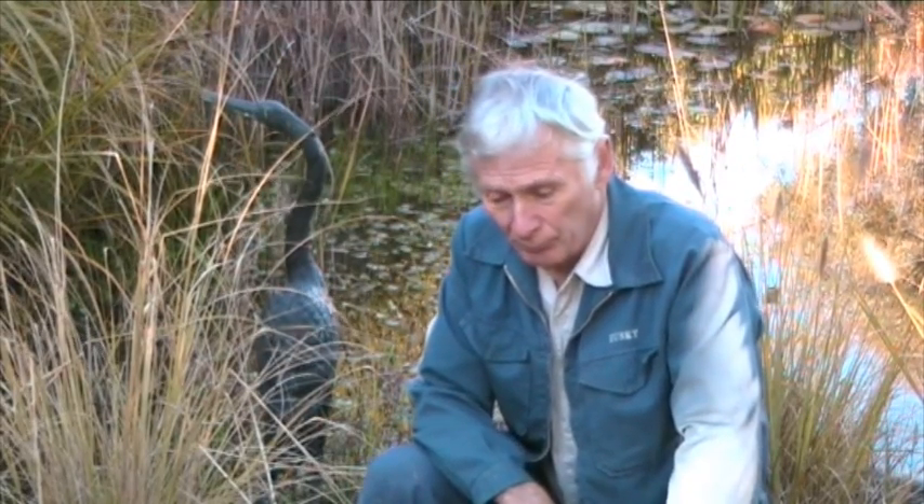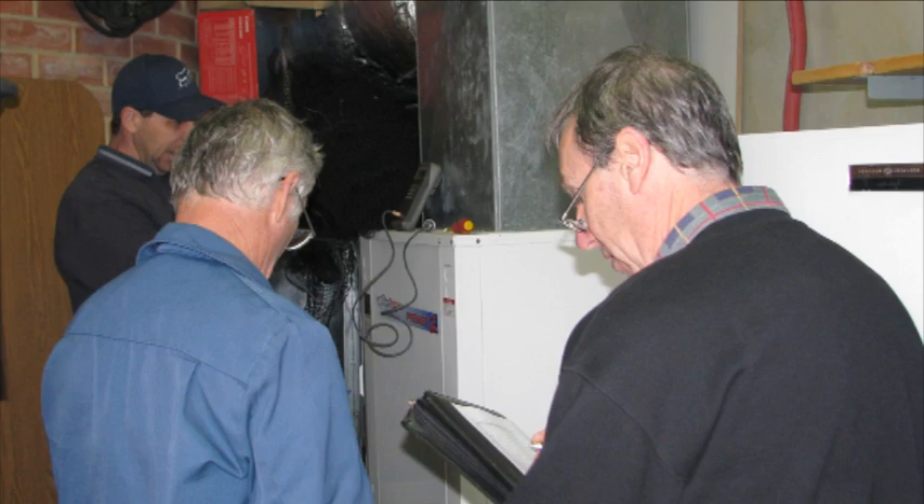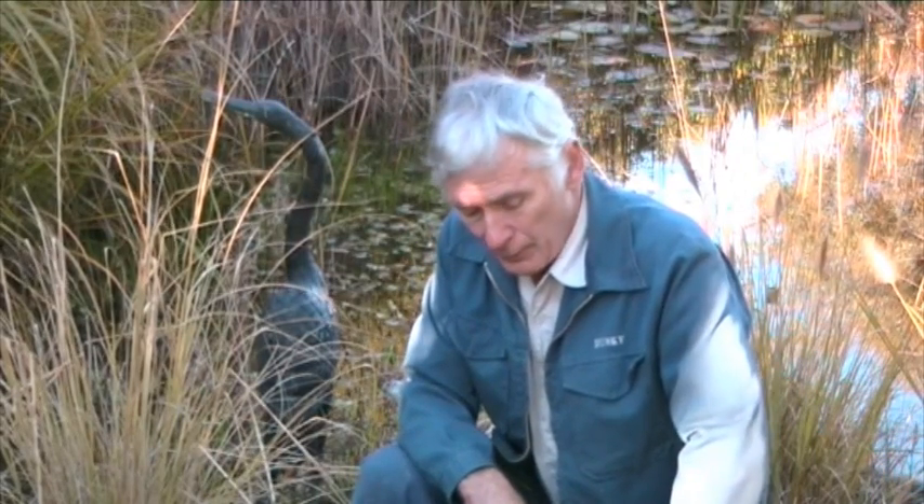So to that end, we brought the people in with the machinery to measure all the parameters. We did measurements before and after — we measured electrical energy to the pumps, because the energy drawn by the pumps is an indicator of how hard the pump is working. The air conditioning geothermal people also did the energy measurements on the efficiency of the heat transfer.